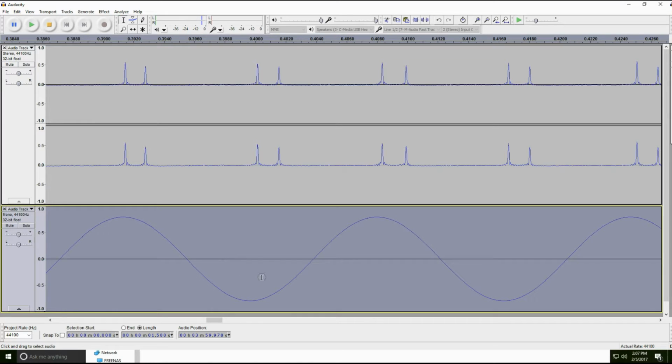But then there's this other burst right at the bottom here where this matches up. And again, and again, and again. So that tells me something. That tells me that I have a power line noise source. The power lines are bipolar, which means they've got a positive peak and a negative peak. And at the positive peak, we're getting an arc or a flash or some kind of tick, we'll call it.